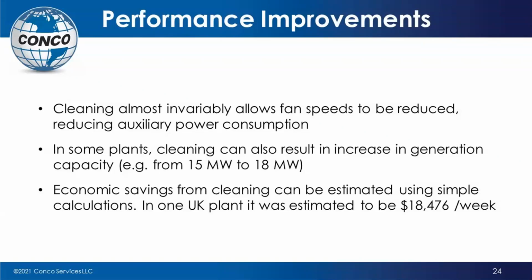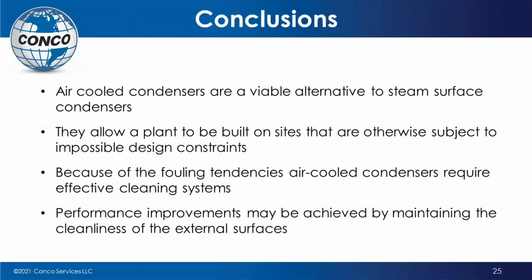We have seen them as high as 15 to 18 megawatts, sometimes a little higher. Economic savings, you can just work it out, but we had one plant in the UK a while back that was saving 18,000 a week. But you can sit down and figure out what it means to you in terms of the fan speed, the amount of draw that you're bringing in, and also how much you can make on the extra megawatts that you're able to sell.